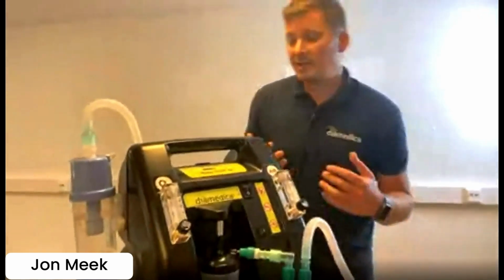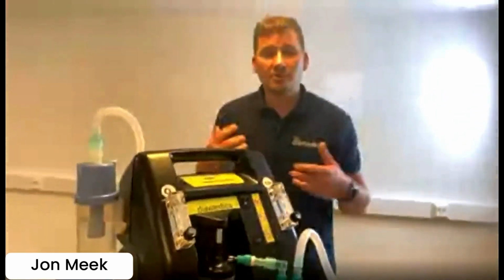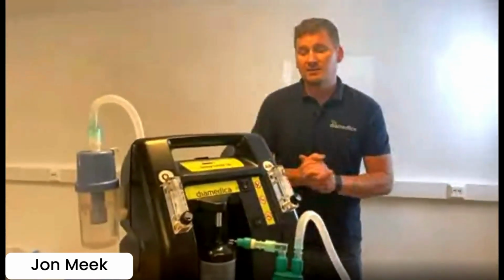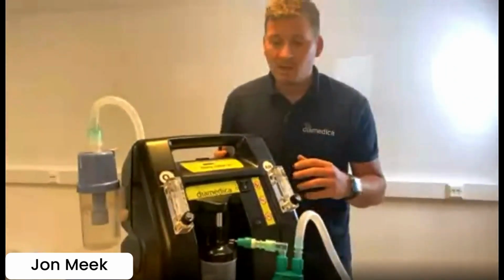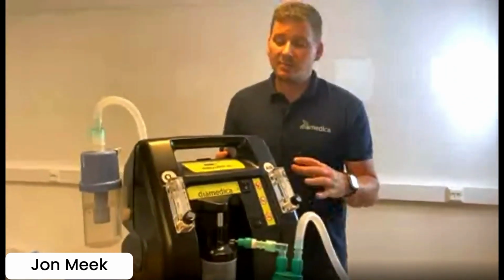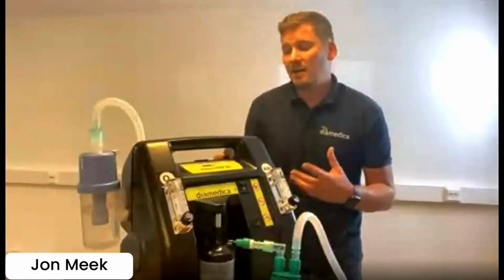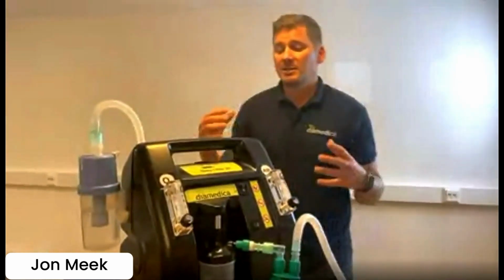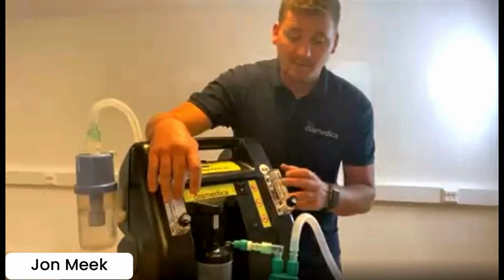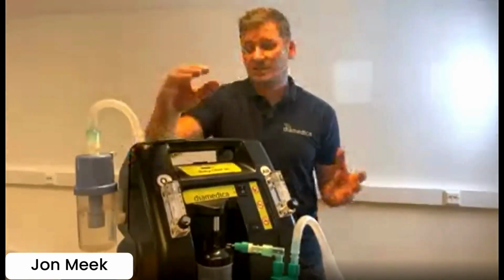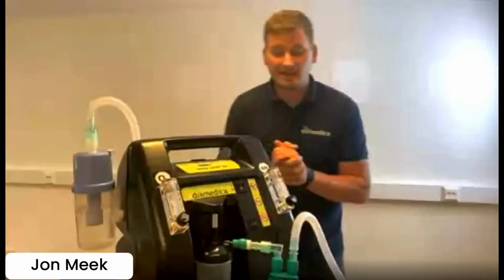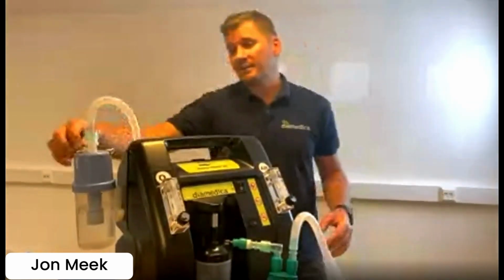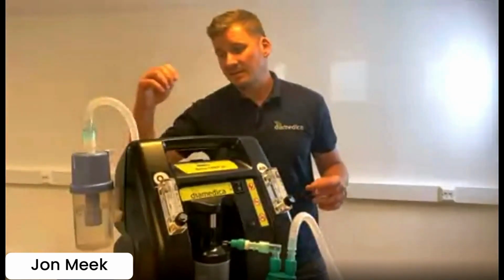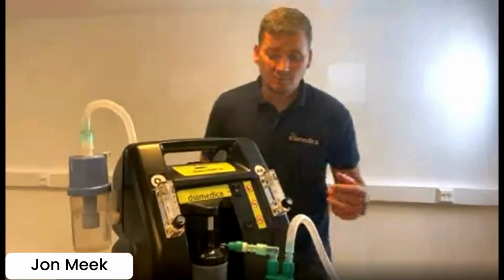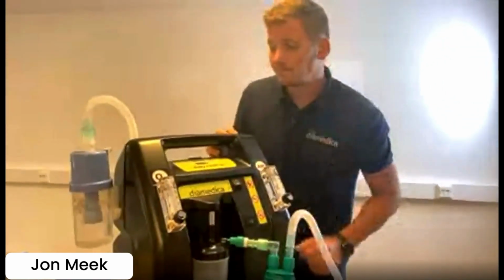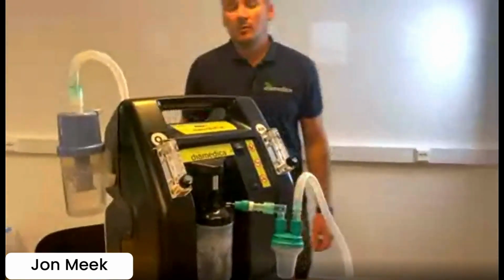Okay, so if I run the machine again, it's already been generating oxygen, so it'll take maybe 10, 20 seconds to build up the pressure. So we're going to look to set the pressure and flow rates as required. I'm just going to set 5 and 5 on my flow meters to give about 60%, or 58% oxygen according to my chart, and I'll set the bubble bottle to 5 centimeters of water. So it's really important when it's running.